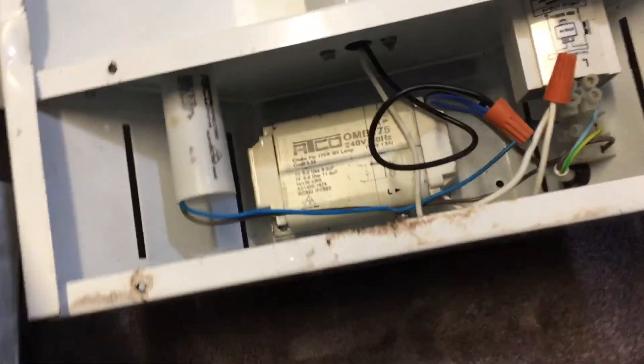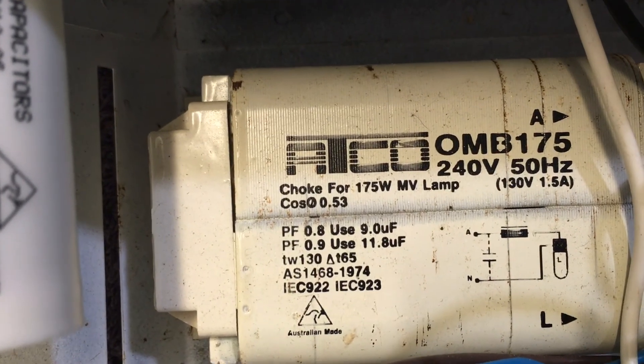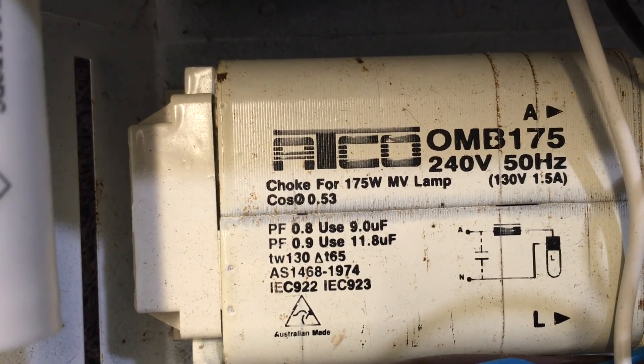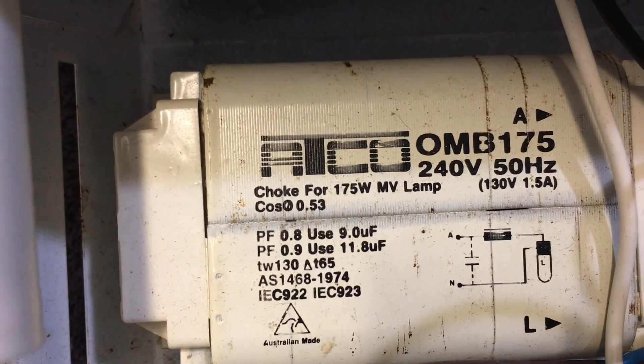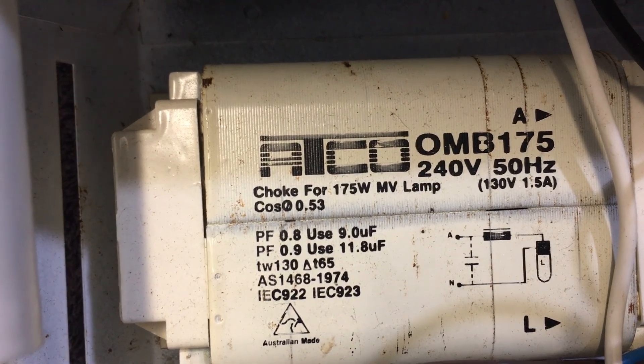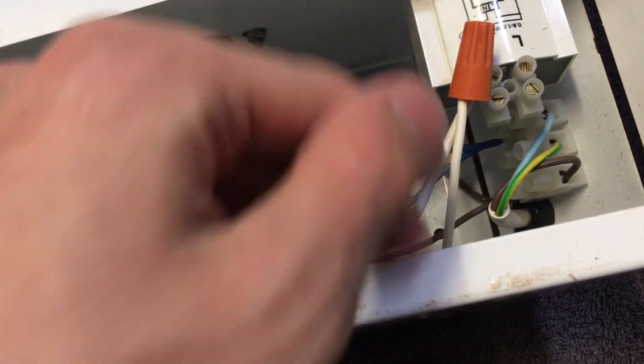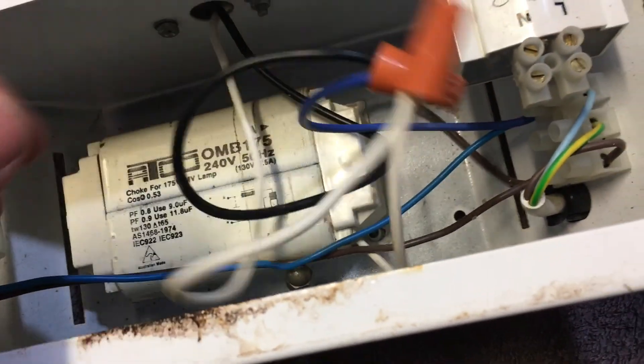Now let's have a look inside — I've unscrewed it; there's usually a bit of glass over the opening. Here we have all our equipment: we have our Atco ballast. It is designed for MV lamps, but you can use it with metal halide if there's an igniter. You can see in the diagram on the ballast there isn't an igniter shown, which I always thought was interesting. Here we have the igniter in the fixture — as you can see, it's not connected. I've tied off the connections so it goes straight from the ballast to the bulb.